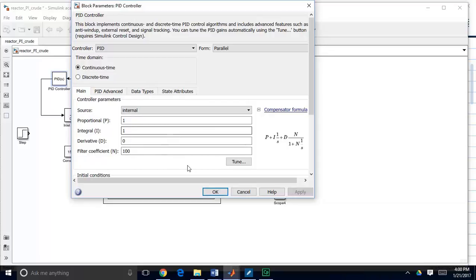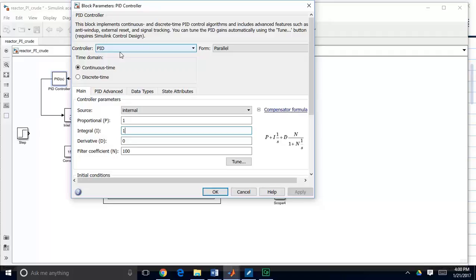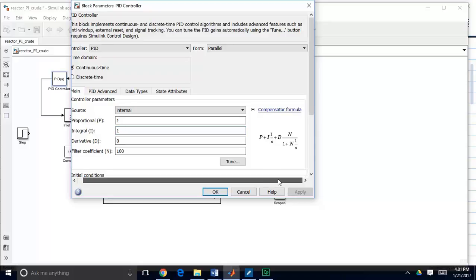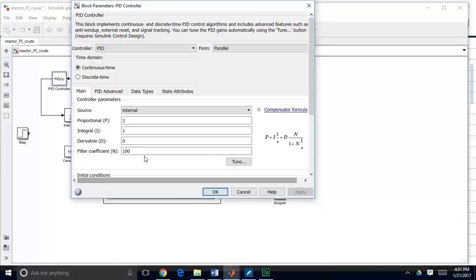Instead of just guessing, we're going to use IMC tuning parameters. In Simulink, P is our proportional controller gain and I is our integral controller gain. This is actually the form for a PID controller, but we're leaving off the D for this class. Derivative control gives the controller more predictive ability, but in practice it's generally easier to stick with a PI controller because a real process can have a lot of noise and you don't want the controller overreacting to that noise. We'll just set the derivative gain to zero.